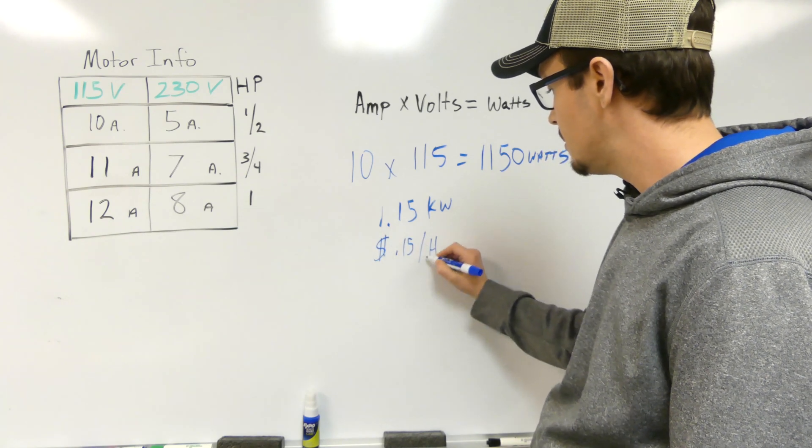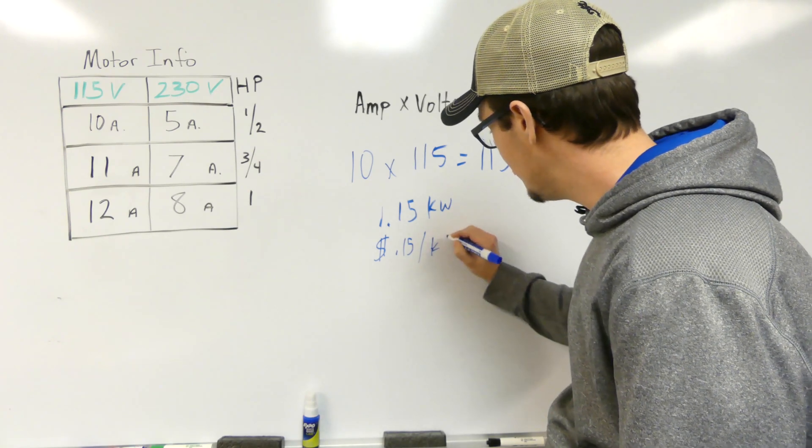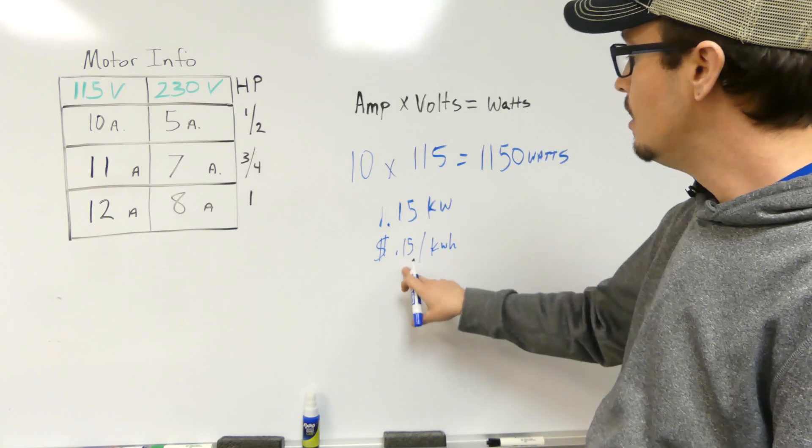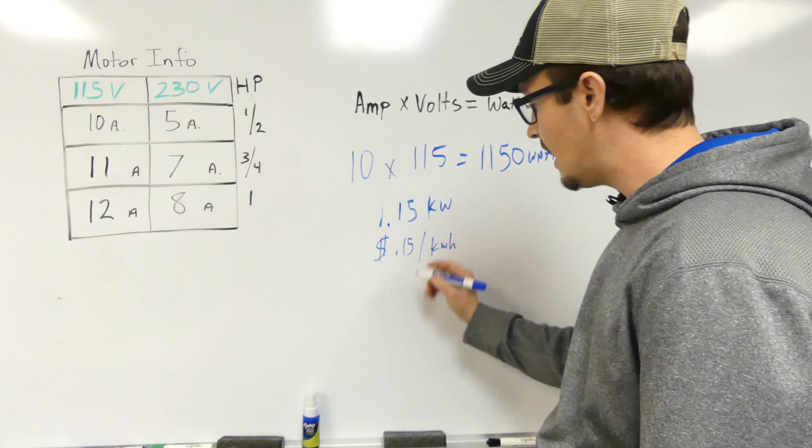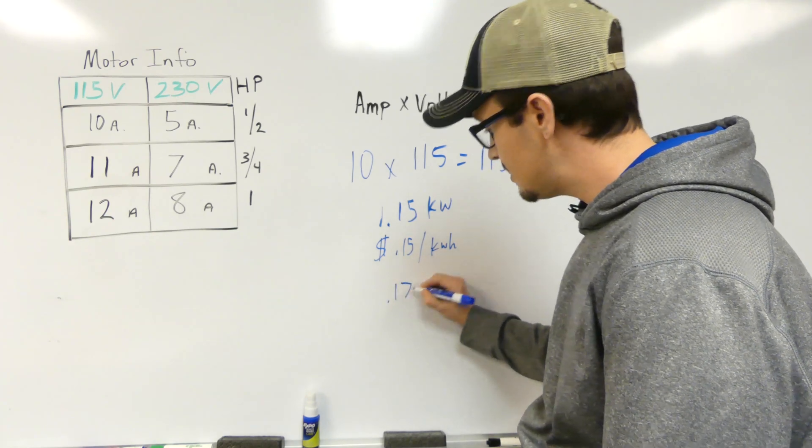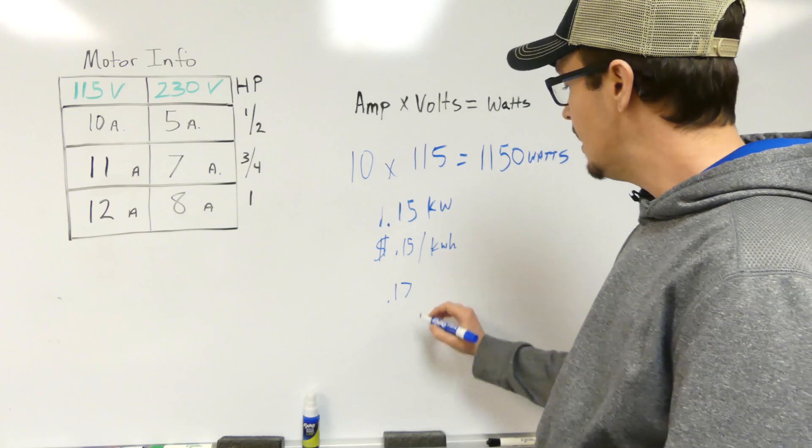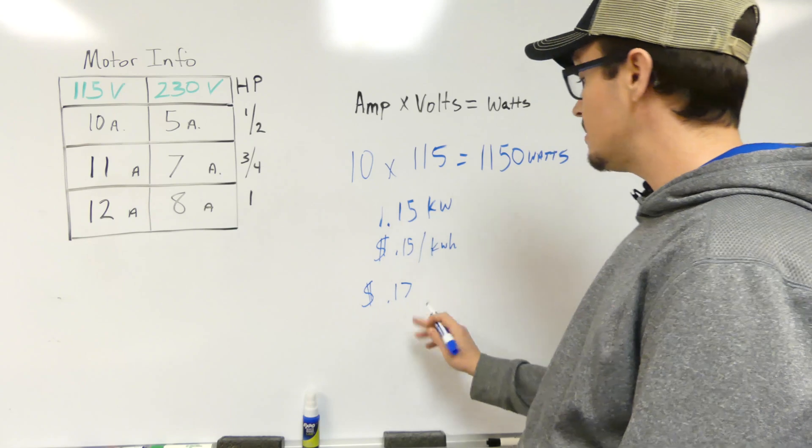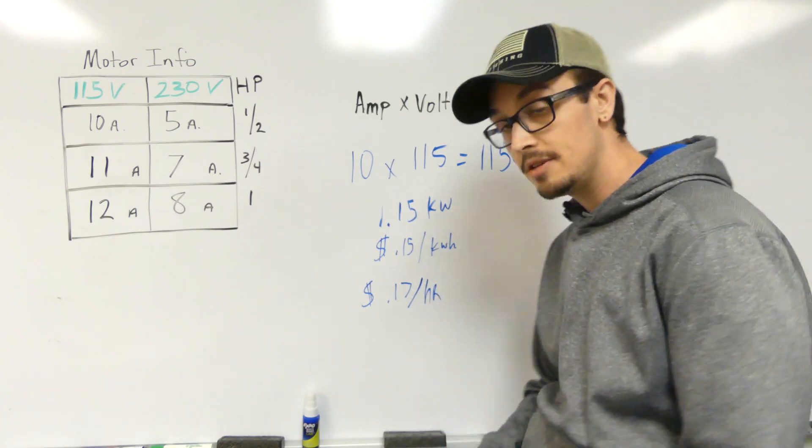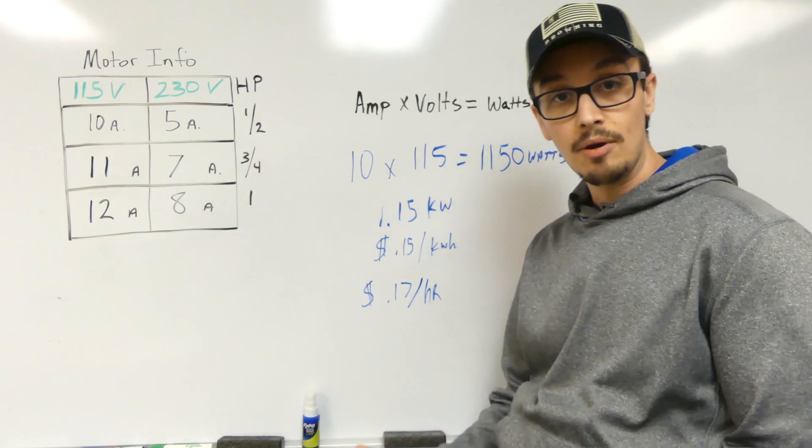So per kilowatt hour, we just multiply 0.15 by 1.15 and we get roughly 0.17, and we're going to just drop the other numbers that come on there. So 0.17, so 17 cents per hour to operate our 115 volt half horsepower pump.